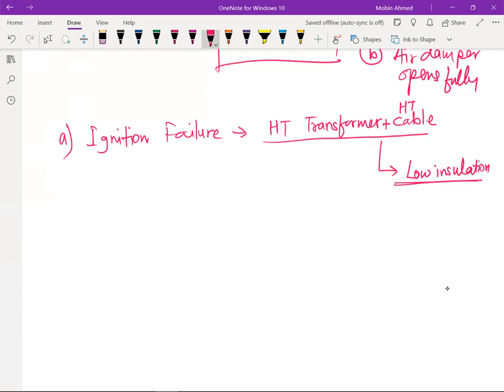HT cables are very soft. Remember that one. So whenever you handle this HT cable, the insulation on top of the cable is a very soft material, so try to handle it very lightly. You should not give any hard turns or anything like that, because it is going to break down. So low insulation will be there due to this. This is one reason. The most common reason is this.